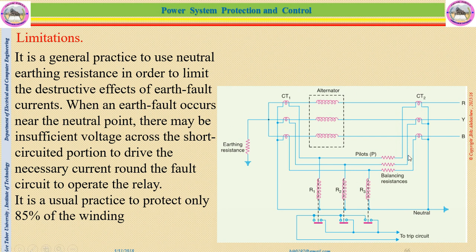Now you can see here this is balancing resistance in order to balance the difference between the two. We added it on the CT2 side because this is found near the switchgear, and most of the time these relay coils are found around the switchgear or near the substations, close to the circuit breaker. This switchgear may be far from the generator. If it is far from the generator, there is high length on the CT1 side, so to compensate the resistance value of this wire, we may add some resistance to balance the two resistances.